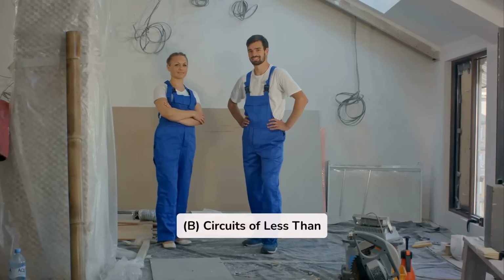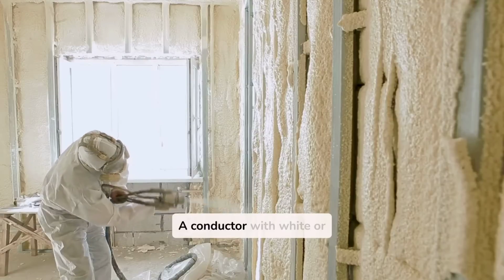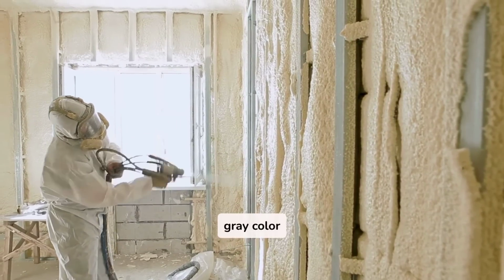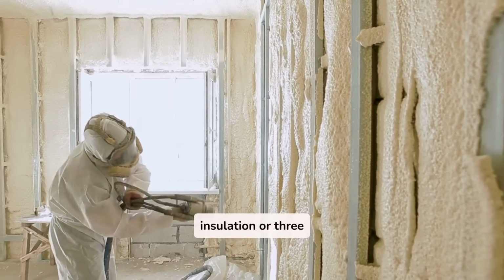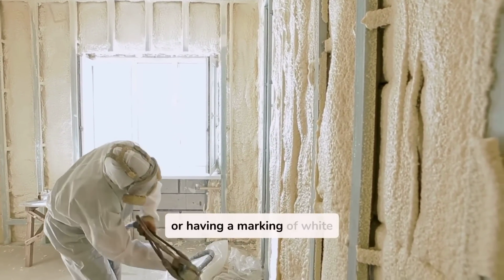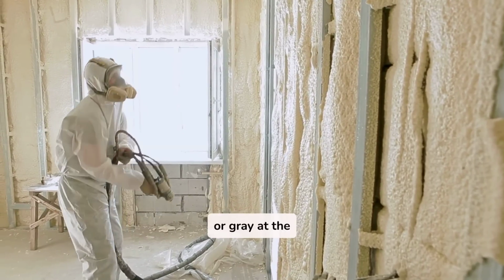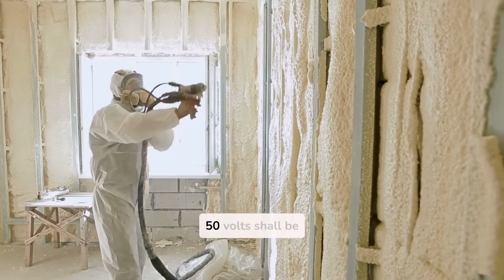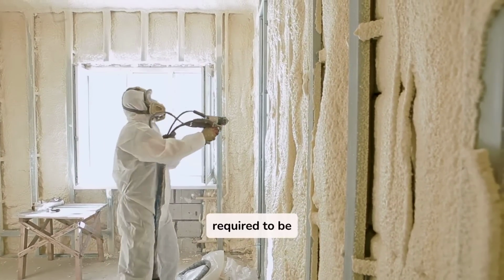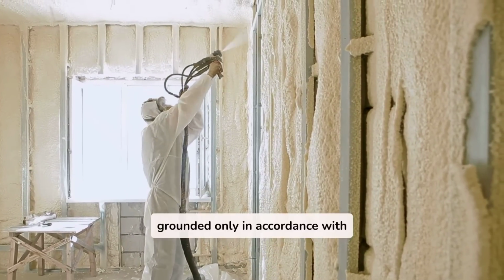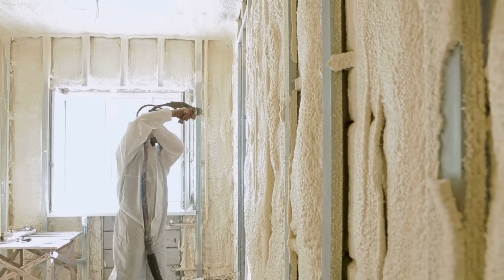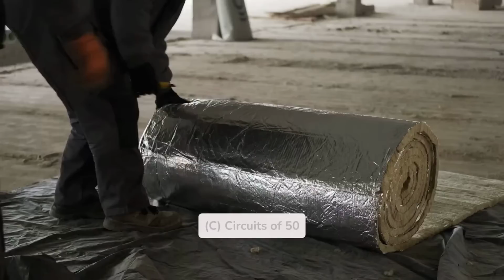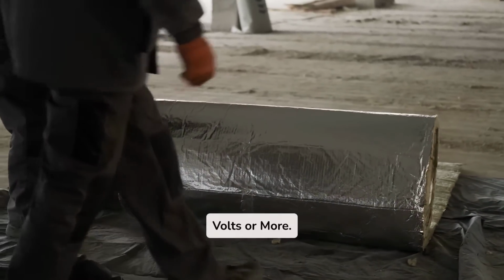B. Circuits of less than 50 volts. A conductor with white or gray color insulation, or three continuous white stripes, or having a marking of white or gray at the termination for circuits of less than 50 volts shall be required to be grounded only in accordance with 250.20 A.